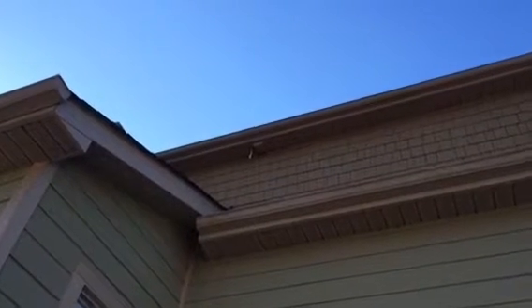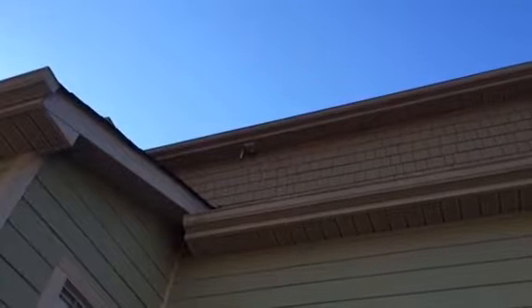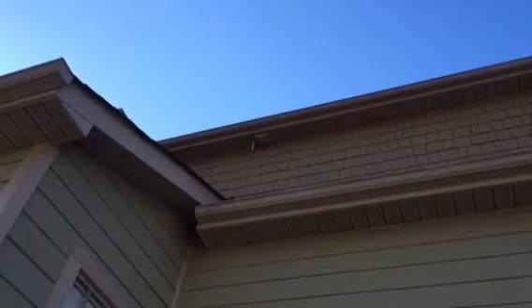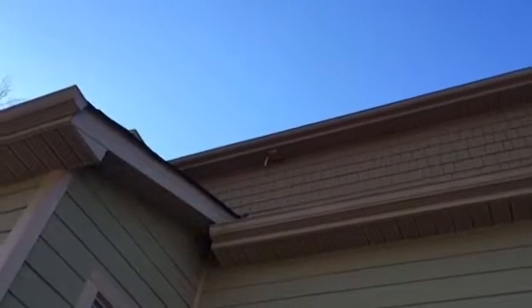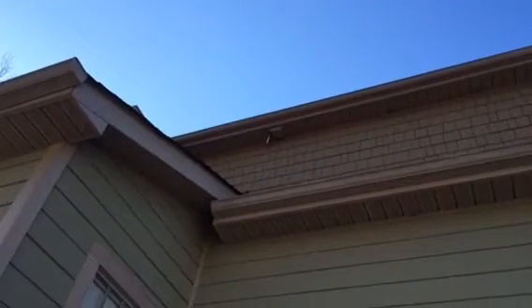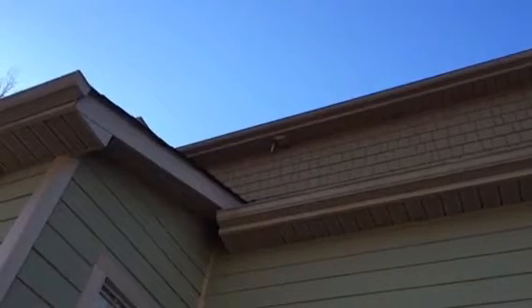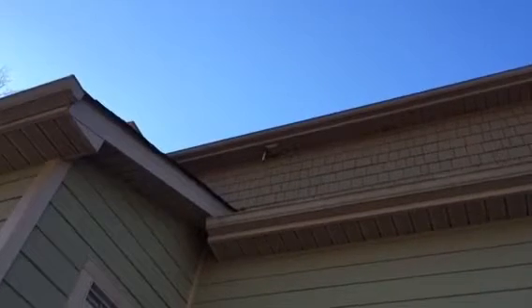With a day in the life of an HVAC tech out here at a customer's house. He's getting ready to sell and the inspection report cited that a new secondary drain was needed. Here is a drain coming out of the attic into the soffit, which is coming off the drain pan. I'll show you where that drain is and that it is coming off of the unit.